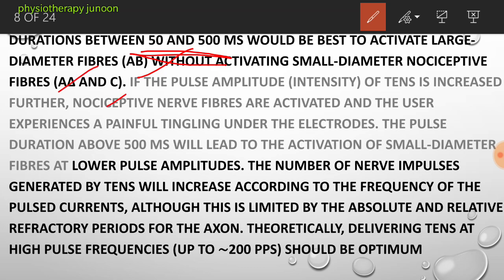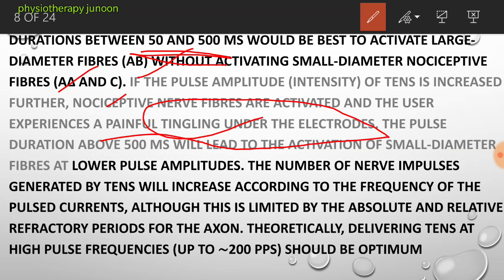If the pulse amplitude is increased further, nociceptive nerve fibers are activated and the user experiences a painful tingling under the electrodes. Pulse duration above 500 microseconds leads to activation of small diameter fibers. At lower pulse amplitudes, the number of nerve impulses generated by TENS increases according to the frequency of the pulse current, though this is limited by the absolute and relative refractory period for the axon. Theoretically, delivering TENS at high pulse frequencies should be optimum.